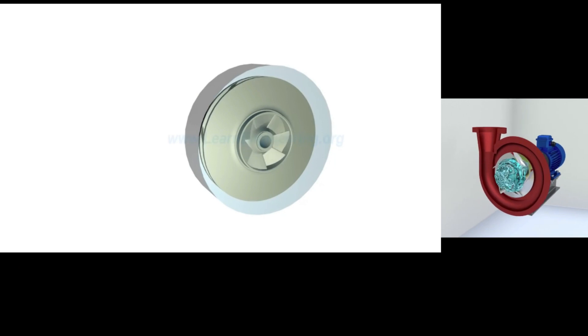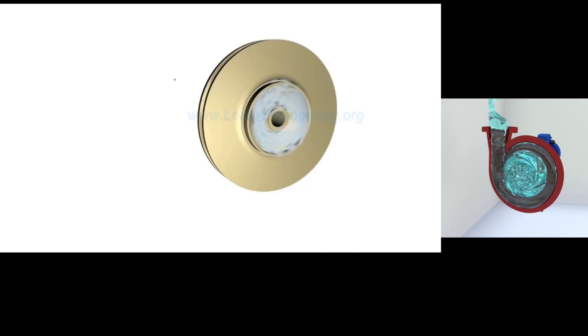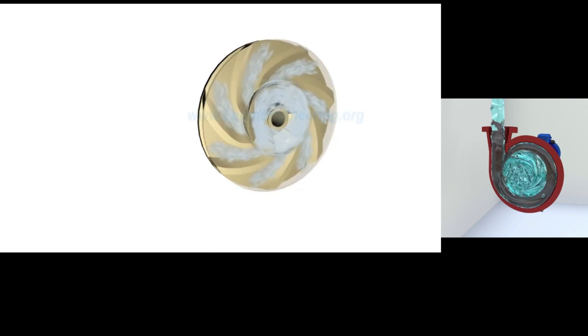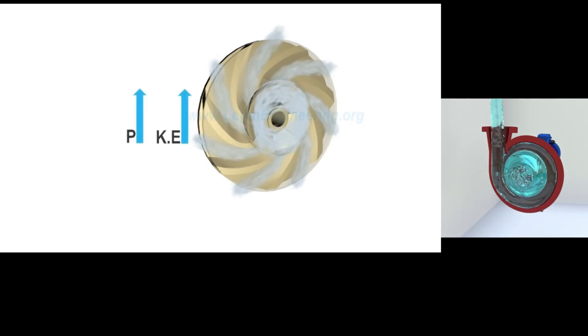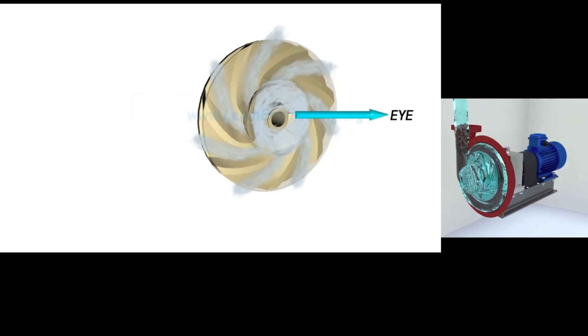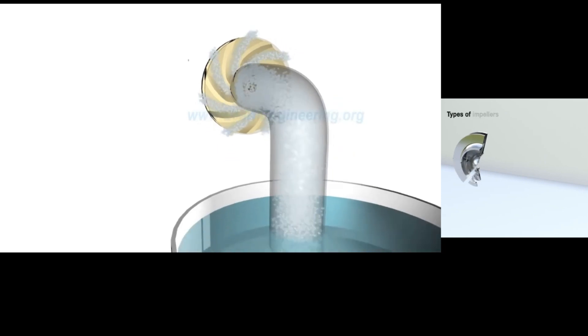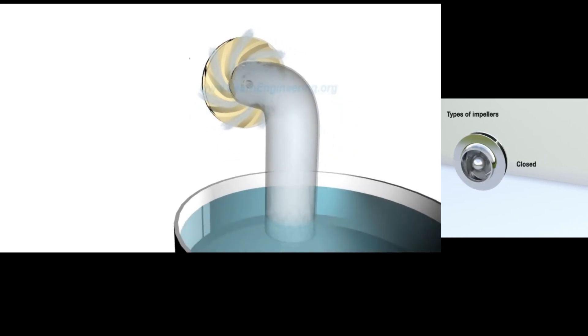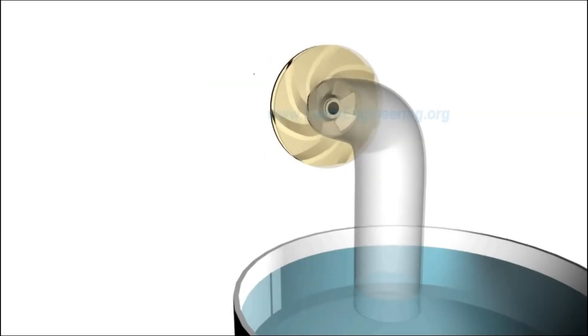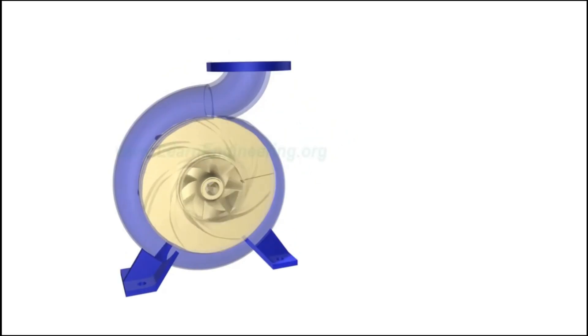The impeller is always immersed in water. When the impeller rotates, it makes the surrounding fluid rotate too, imparting centrifugal force to the water particles, which then move radially outward. At the discharge side, both pressure and kinetic energy rise. At the suction side, water is displaced, creating negative pressure that helps suck fresh water into the system.